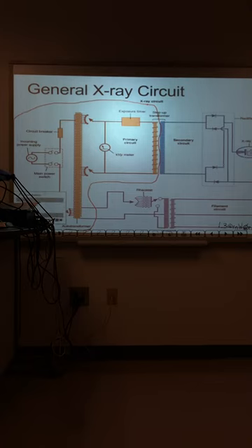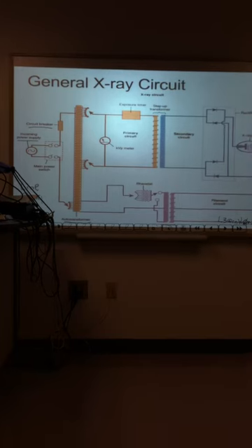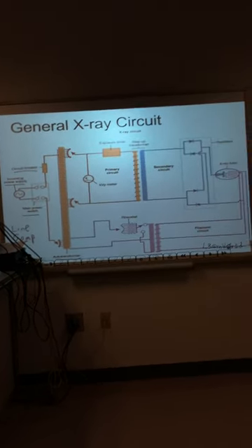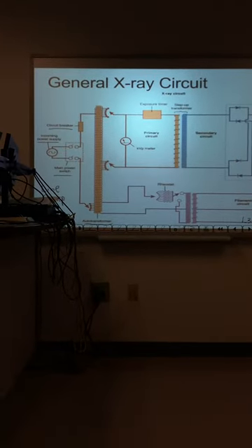Can you repeat the question and the answer? All right. If you have the question to explain what's occurring in the primary circuit of the X-ray tube, what four components did I just talk about? I talked about the incoming line supply. The line compensator. The line compensator is in here. Circuit breaker. That's connected to the auto transformer. Circuit breaker, auto transformer. And the line compensator. That was four.